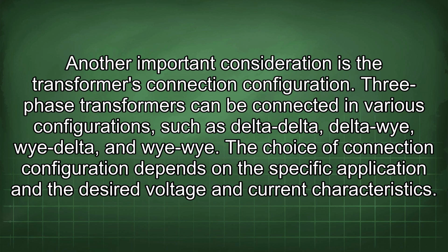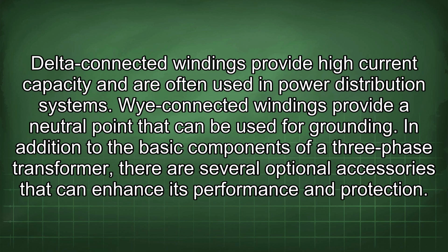Another important consideration is the transformer's connection configuration. Three-phase transformers can be connected in various configurations, such as delta-delta, delta-Y, Y-delta, and Y-Y. The choice of connection configuration depends on the specific application and the desired voltage and current characteristics. Delta-connected windings provide high current capacity and are often used in power distribution systems. Y-connected windings provide a neutral point that can be used for grounding.